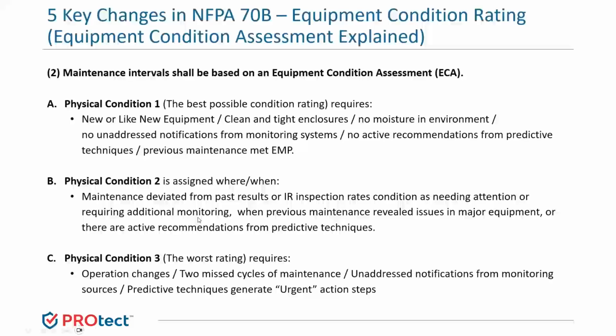And then on the next slide here, we just have the 3 physical conditions listed out with identifiers for each of those conditions. Again, like I mentioned, physical condition 1 is the best possible rating. This is going to be for your new components or your components that appear in a like new condition. The enclosure is free of moisture, clean, and tight. There are no unaddressed notifications from continuous monitoring systems, and predictive maintenance techniques do not generate active recommendations. So in other words, all previous maintenance has been performed in accordance with your electrical maintenance program, and there aren't any outstanding actions on that.